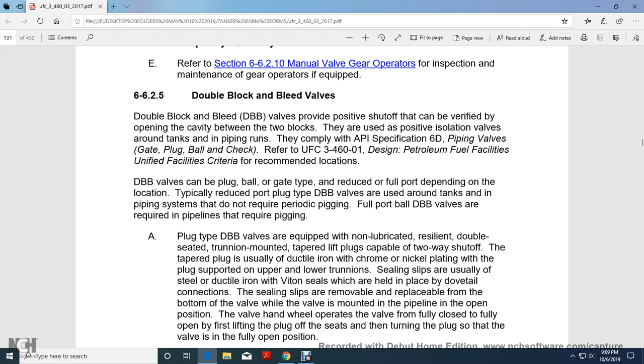Double block and bleed valves can be plug, ball or gate type, and reduced or full port depending on the location. The reduced port double block and bleed valves are used around tanks and piping systems that do not require periodic pigging. The full port double block and bleed valves are required with pipelines that require pigging.